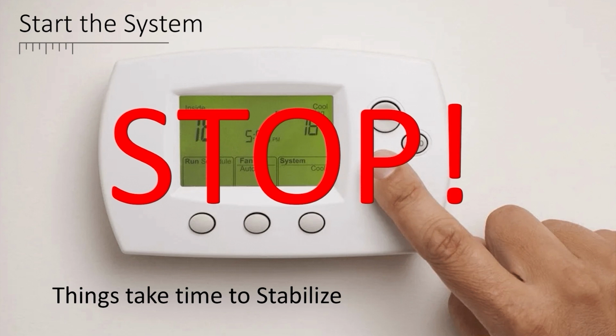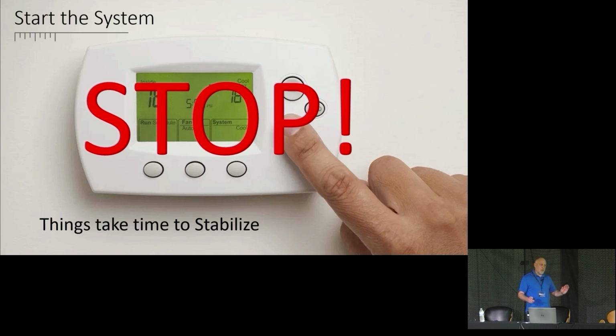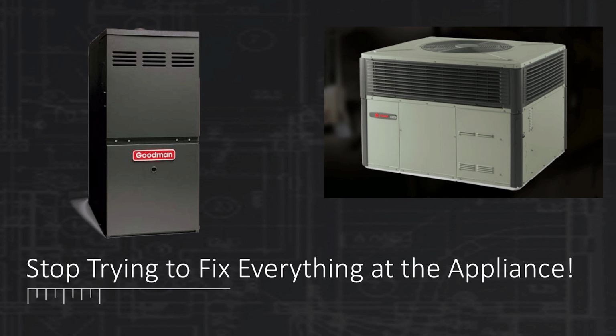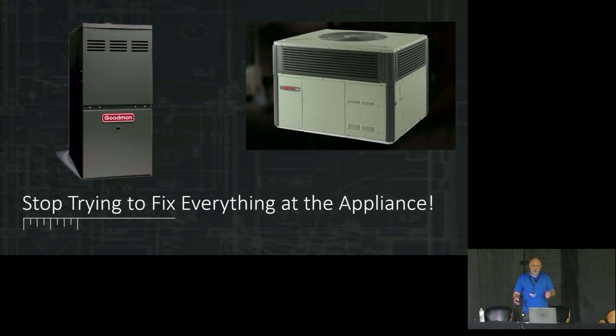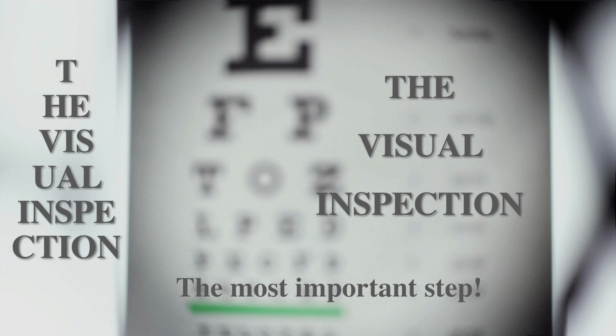But here's where I want you to completely stop what you're doing and think about what's going on with the entire system. The challenge is everybody in our industry tries to fix everything at the appliance, right? You go out there, you do a startup, you're trying to set the airflow at the appliance, you're setting the gas pressure, manifold pressure, temperature rise, you're going through on an air conditioning system doing the charge, but people don't take the time to look at the entire system. And so what we're going to talk about a little bit first is the visual inspection.